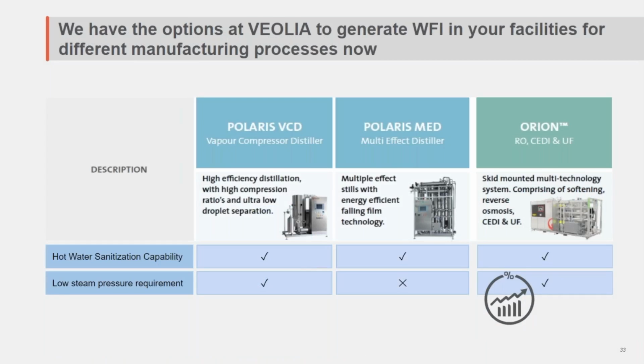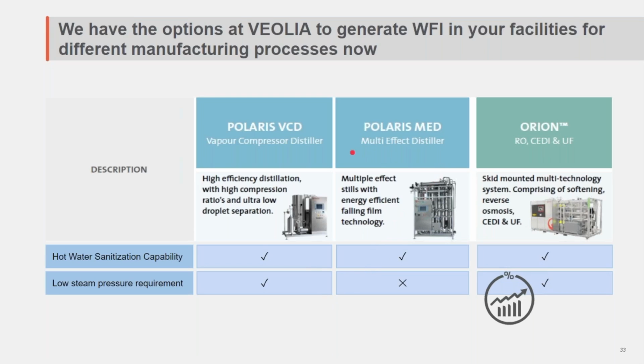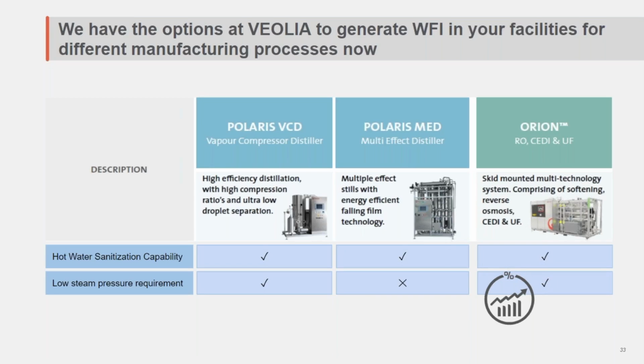Okay, and here we have the comparison between the 3 units in terms of hot water sanitization, low steam pressure, which obviously the Polaris MED can't allow. I mean, the 3 technologies are available, and we would guarantee quantity and quality of water from all 3. So it all really comes down to risks perceived by you, the customer, the OPEX, the amount of steam availability on site, and how important energy saving is. So all 3 have their merits, and all 3 have some of their concerns as well. But what we can say from all 3, as I say, we can guarantee quantity and quality of water to WFI specification. So there are alternatives to the traditional distillation units.